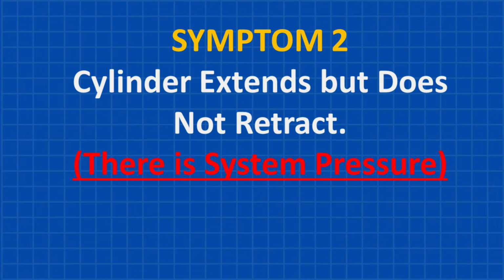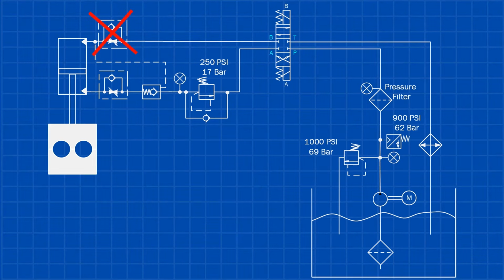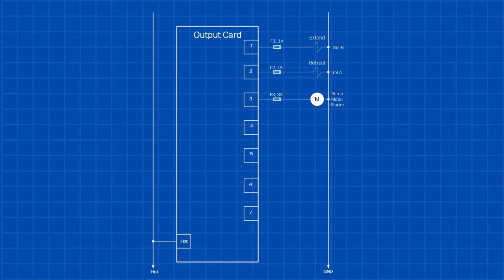Symptom 2. Cylinder extends but does not retract, and we have system pressure. This is almost never a flow control issue, unless the flow control valve is set to maximum restriction, in which case the cylinder will still retract, but very slowly. So what is the issue? First, ensure that power is reaching the coil. Check the fuse. If it's blown, this indicates a shorted solenoid coil. In that case, replace both the coil and the fuse.